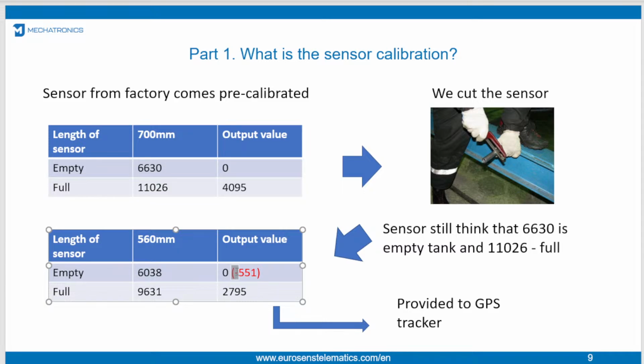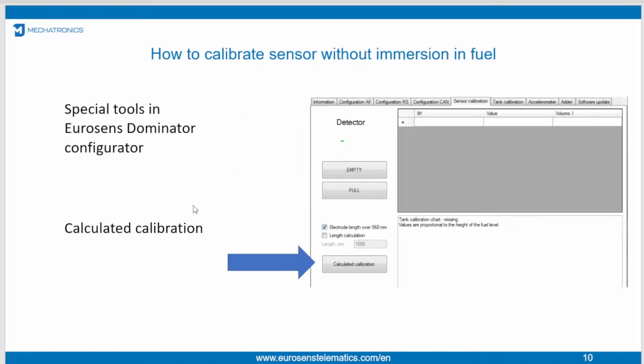We teach the sensor its new height or length. After sensor calibration, the sensor restores its default output range, no matter how we cut or extend the sensor. And calibration doesn't always mean immersing the sensor in the fuel. We have some tools in our configurator to skip this procedure in most cases.